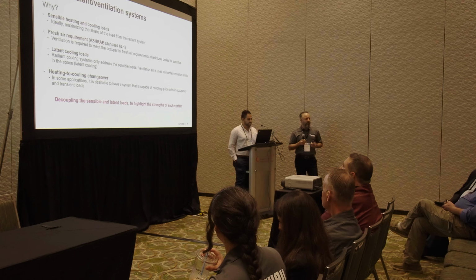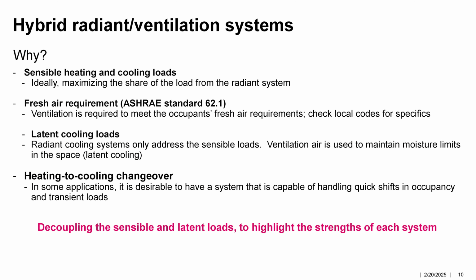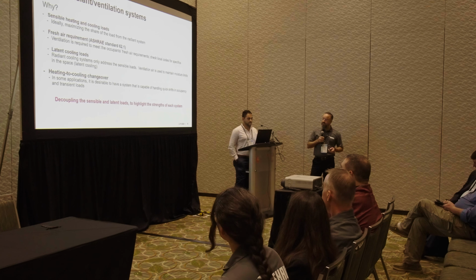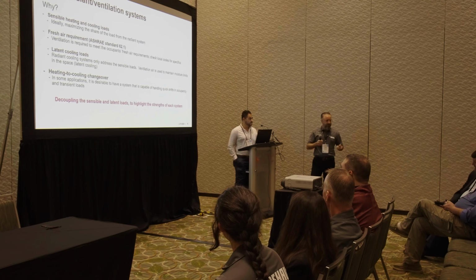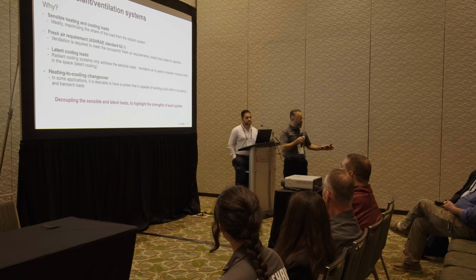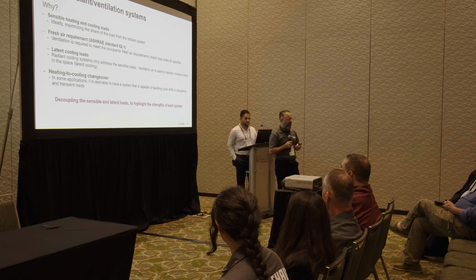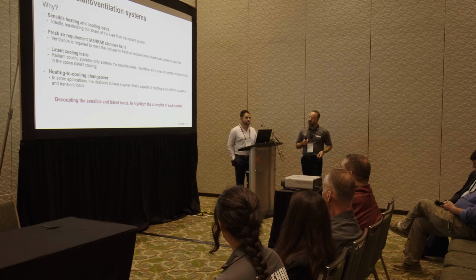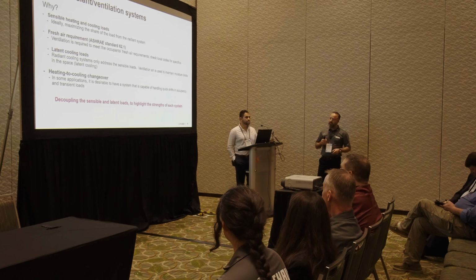First of all, radiant cooling system is a limited source of cooling. By that I mean it can address, on a good day, the whole sensible load or a portion of the sensible cooling load, but you need an air system to cover the latent cooling load, which is technically the moisture in the air. And also, based on ASHRAE 62.1, you need some sort of fresh air. Say we have radiant cooling in this room, we need to provide a certain amount of air changes per hour to meet that ASHRAE standard. That's the second reason. And also the changeovers.